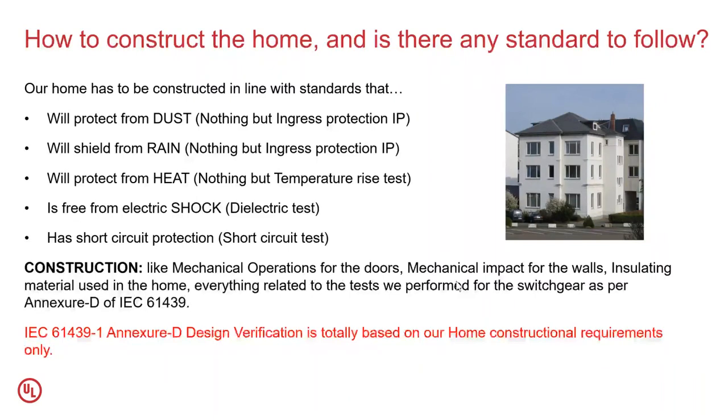It has to be free from electric shock. Nothing but I am going to do a dielectric test in our IEC standard. Any short circuit inside my home has to be protected. Hence, my switchboard also undergoes a short circuit test. And all my doors and hinges have to be mechanically constructed in line with the requirements. Same way, my switchboard also has to have a construction verification, like mechanical operations or mechanical impact, insulating materials. Everything has to be constructed in line with the constructional requirements of IEC 61439.